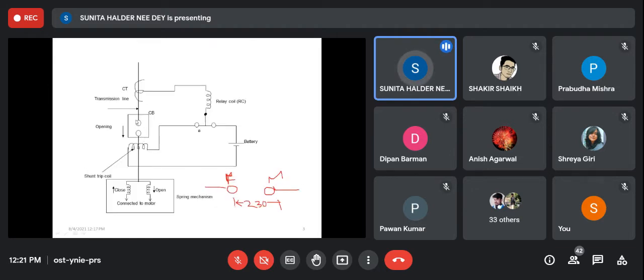So what should be the capacity of a circuit breaker? At normal, closed condition, it should be capable of carrying the system current. At abnormal condition, when it has not yet opened, it should be capable of carrying the short circuit current. When it is open, it should withstand the system voltage across its terminals. That's why, depending on the voltage rating or power rating of the circuit breaker, along with current, the circuit breaker may have an insulating medium like oil, vacuum, or air if it is of low rating. So in this way, there are different types of circuit breaker. Professor Sudipta Nath will tell you about this in the other part.